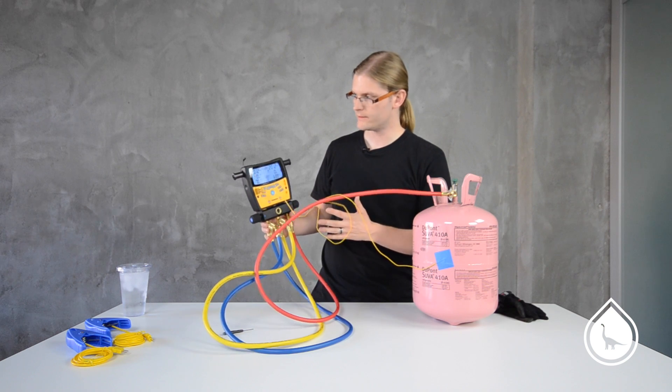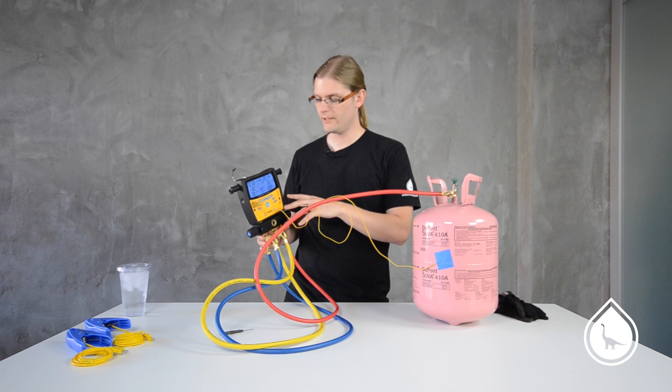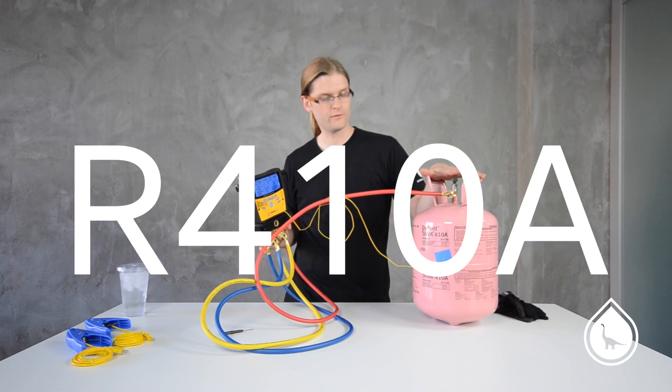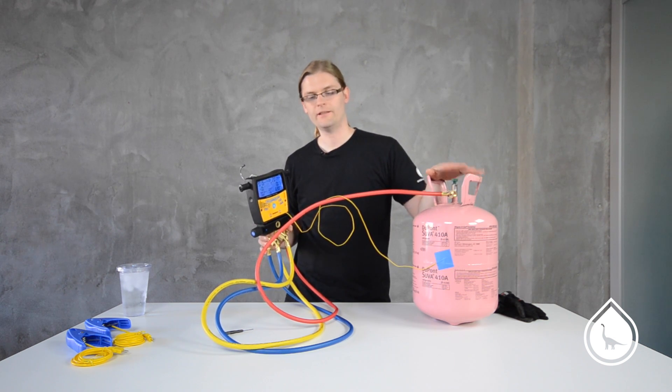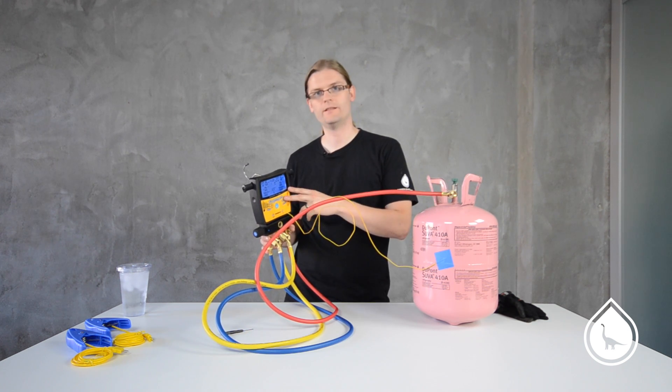When it runs this test, it's taking your measured pressure and your measured temperature and comparing it to a pressure temperature chart for R410A. If it gets too far off of what the chart should be saying, then it's going to tell you it's out of calibration.